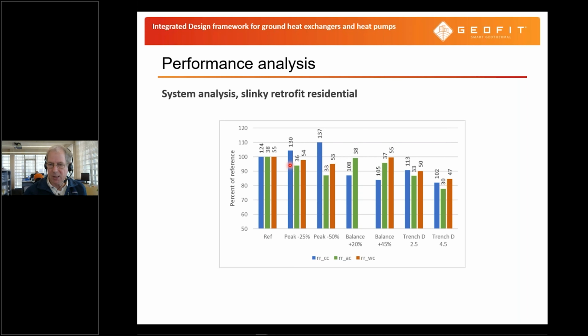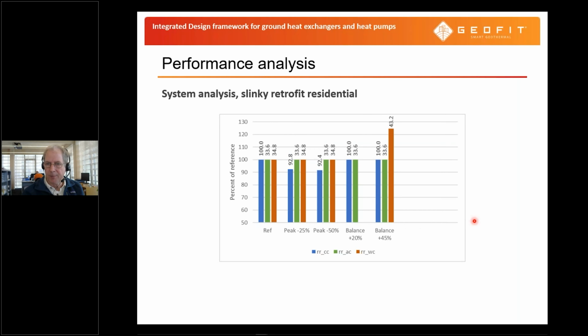So for the cold climate, you can see that if we vary the peak load by 25% higher peak load, we obviously increase the total length of the system. For the 50%, it's even more. And then if we look at the balance, you can see that we reduce the length. For a higher balance, it's a slightly larger effect. And the trench depth also has an effect on the overall length required to achieve the same performance factor. The same we did for a slinky retrofit residential.